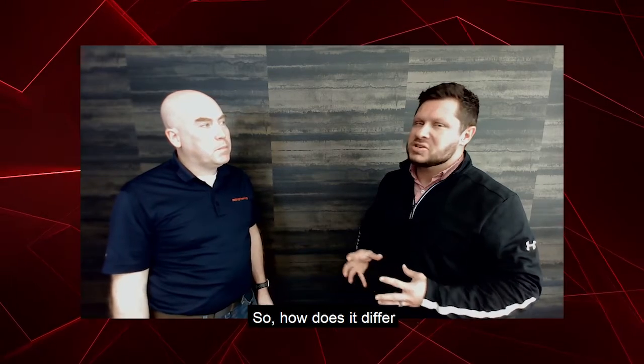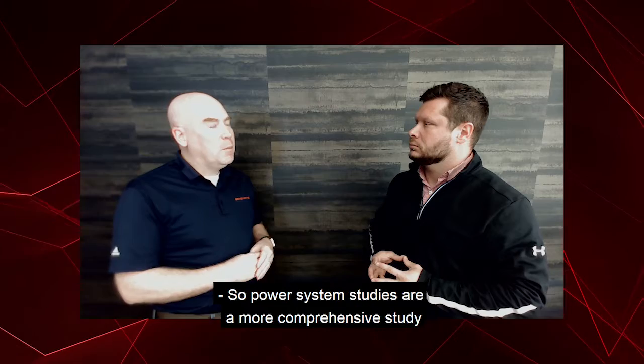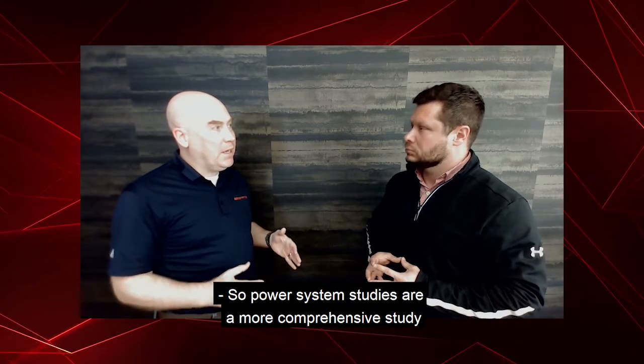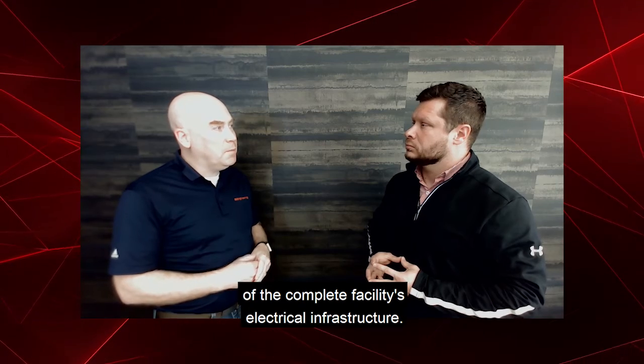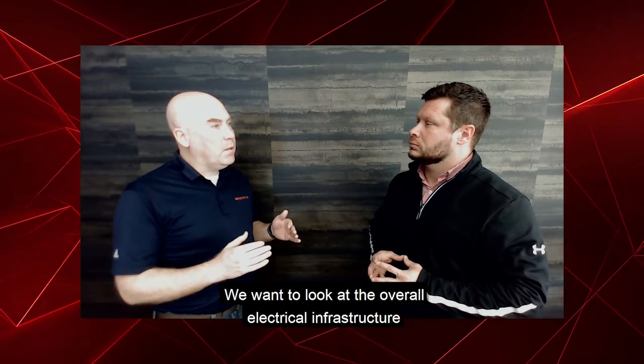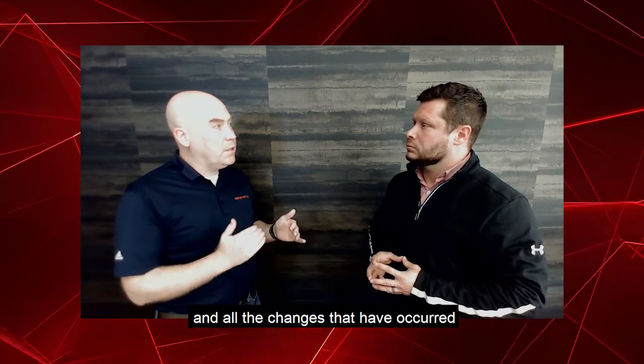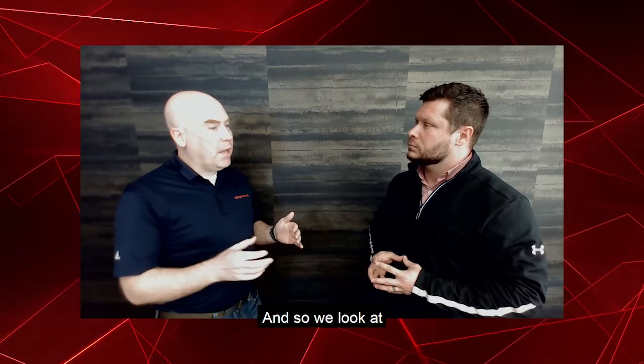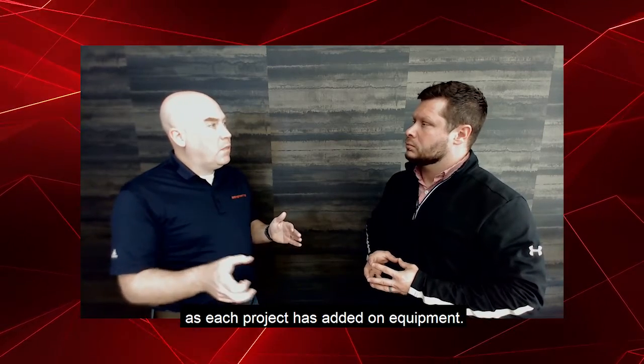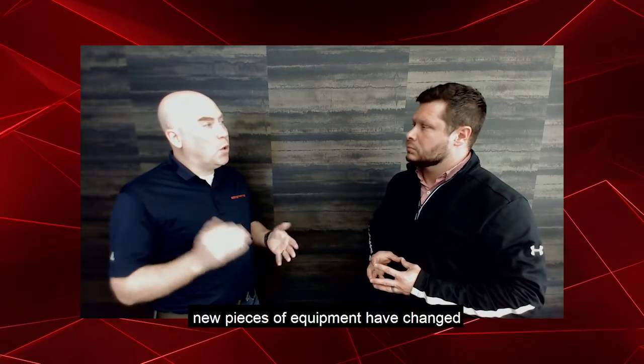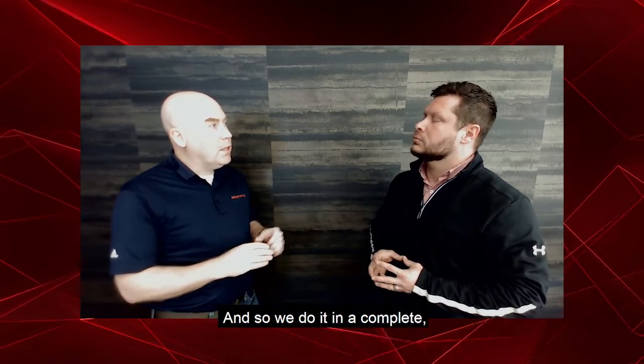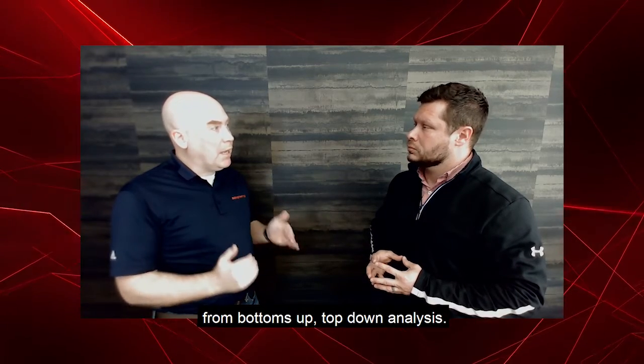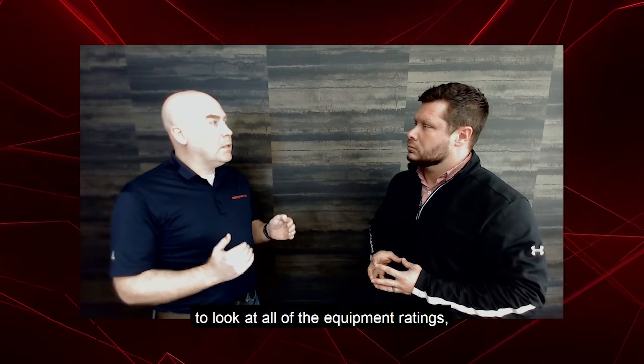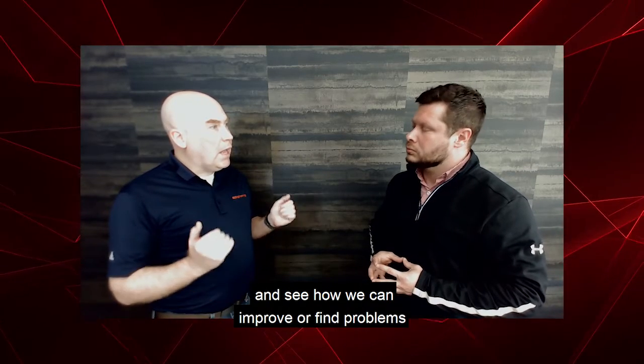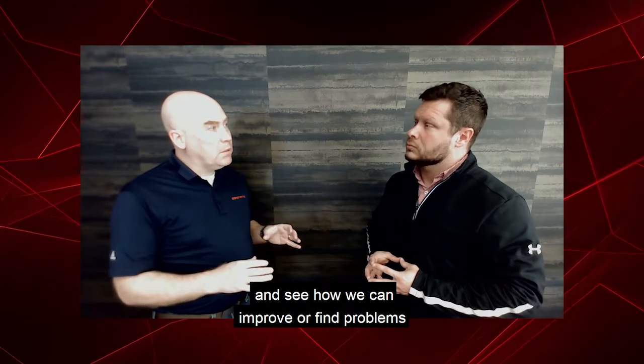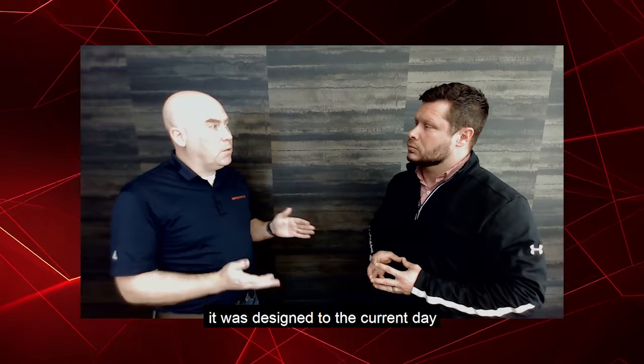Sure, so how does it differ from an arc flash study specifically? Power system studies are a more comprehensive study of the complete facility's electrical infrastructure. We want to look at the overall electrical infrastructure and all the changes that have occurred since it was first designed—as each project has added on equipment, new loads have been added, new pieces of equipment have changed, or maybe even the utility service has changed over time. So we do a complete bottoms-up, top-down analysis to look at all of the equipment ratings, the coordination between the different levels, and see how we can improve or find issues that have arisen since the time it was designed to the current day.